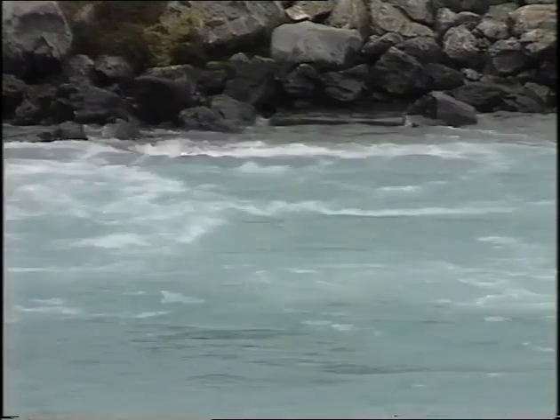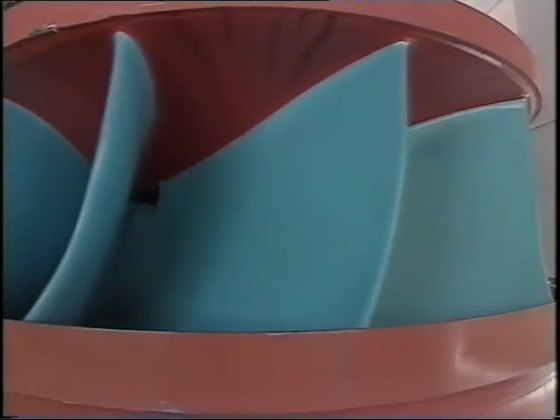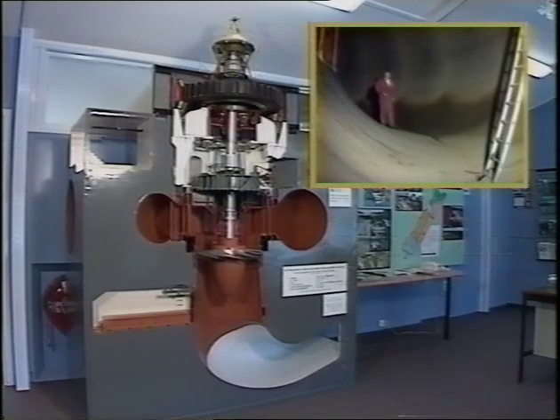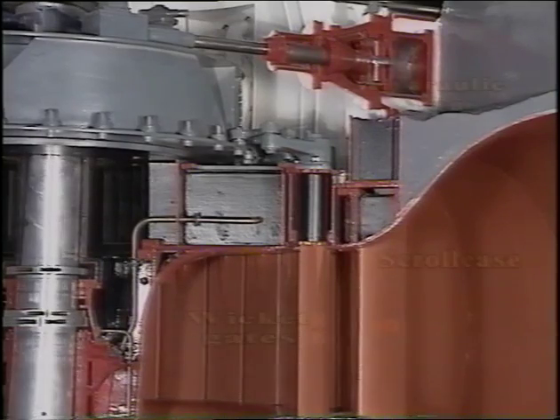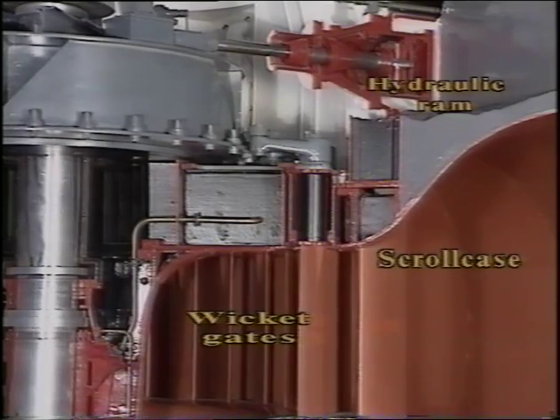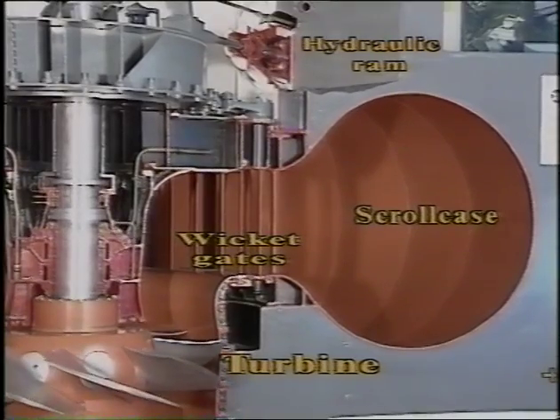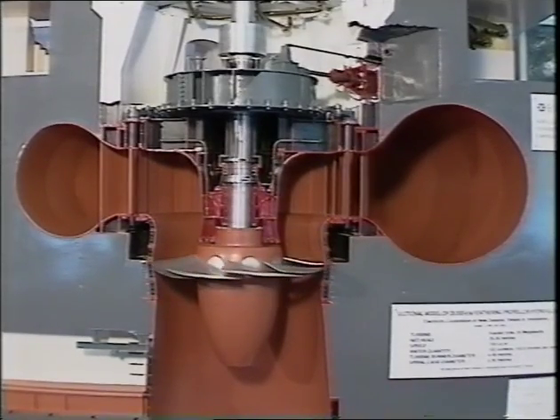So just how does the water make electricity? Well, to tell the truth, it doesn't — water does not make electricity. What water does do is turn turbines. By operating a hydraulic ram, wicket gates can be opened and closed. When opened, the gates direct the water against the turbine blades, forcing them to start turning, and after about half a minute the turbine reaches its operating speed of exactly 166.7 revolutions per minute.